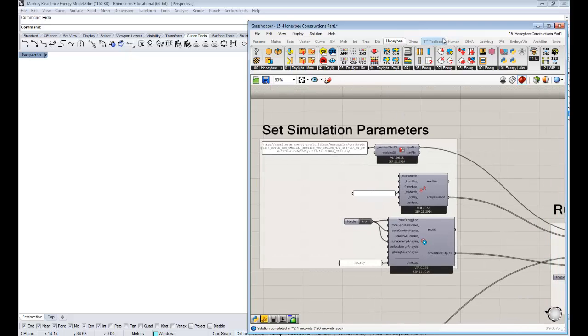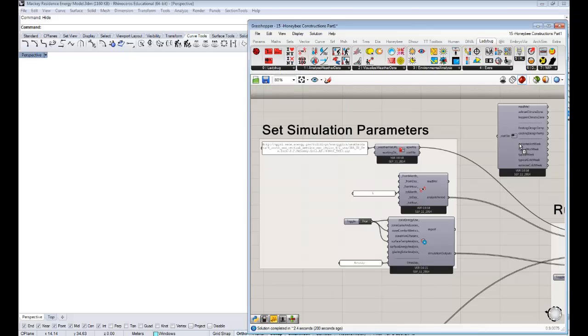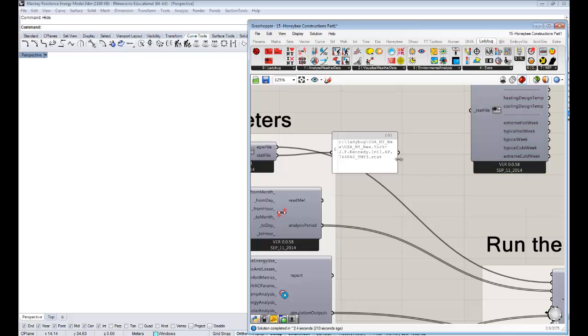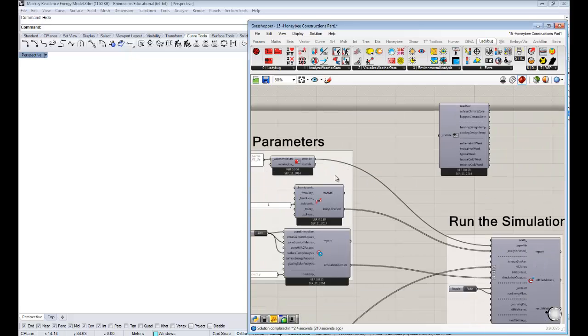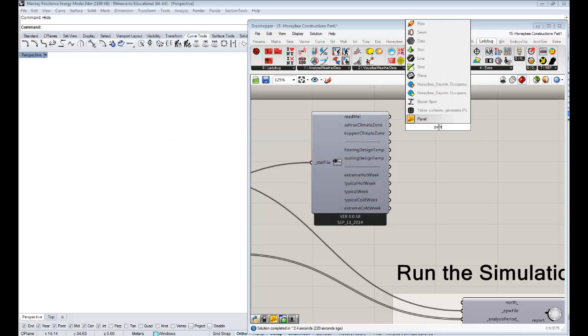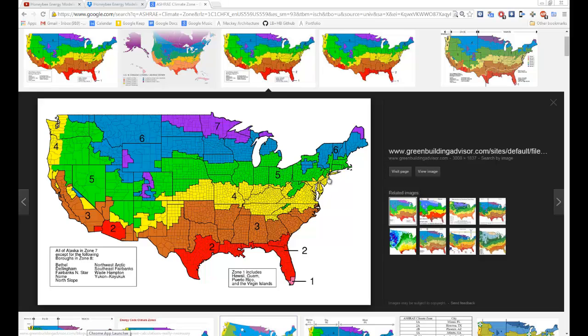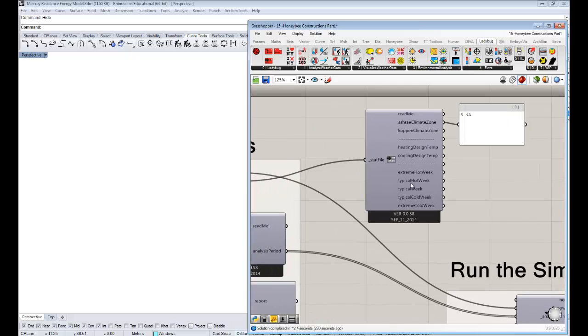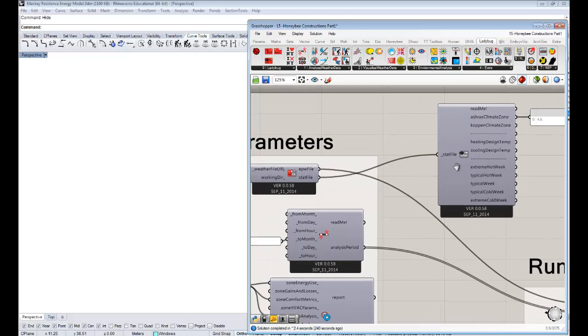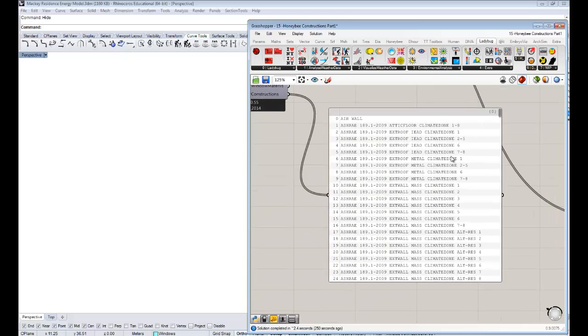Under Ladybug, there's actually a component that will tell you your ASHRAE climate zone — it's the import stat component under zero Ladybug. When we used this component in the past, it brought in a stat file. If you hook that up into the import stat file component, one of the outputs is ASHRAE climate zones. We're looking at New York right now, and that's ASHRAE climate zone 4A — which is true to the map. Any EPW file over the entire planet will have an ASHRAE climate zone in its stat file, even if it's not in the US. You can use that as a basis to select constructions from the library.